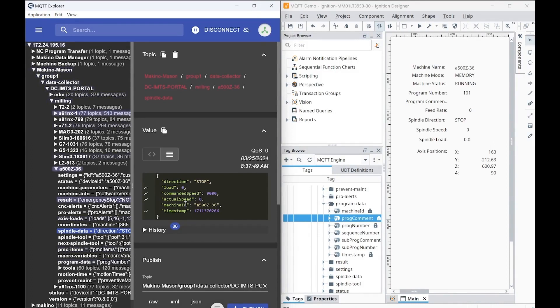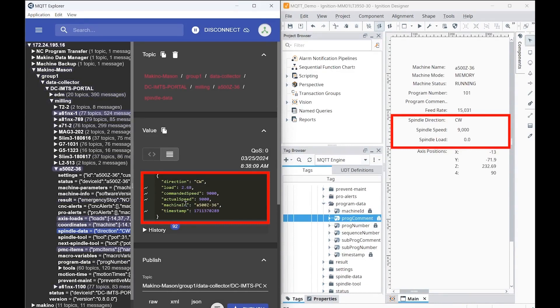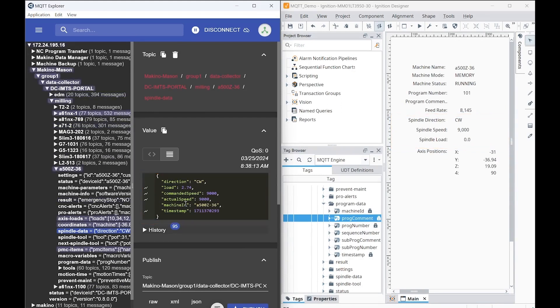If you watch on the left side in MQTT Explorer, you'll see the spindle speed just increased to 9,000 RPMs, as well as in Ignition. If you pay attention to the load, you'll see it's hovering around 2.5 percent in MQTT, but in Ignition it's staying at zero. We'll come back to this issue later.